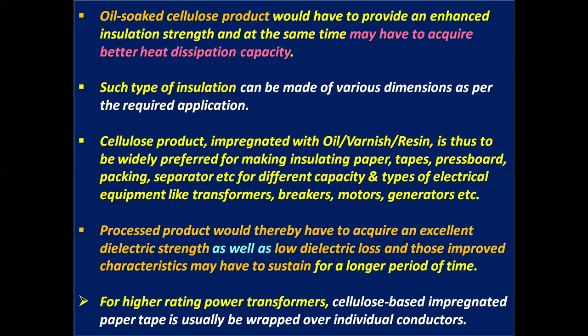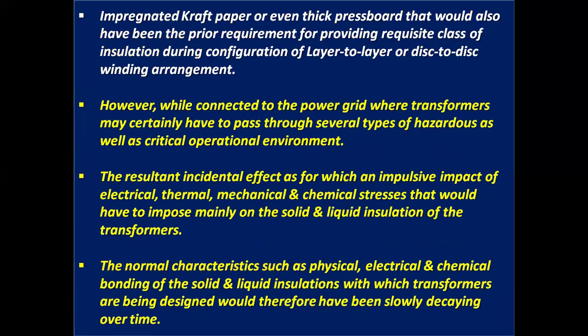For higher rating power transformers, cellulose-based impregnated paper tape is usually wrapped over individual conductors. Impregnated kraft paper or even thick pressboard is also a prior requirement for providing the requisite class of insulation in layer to layer or disc to disc winding arrangements.